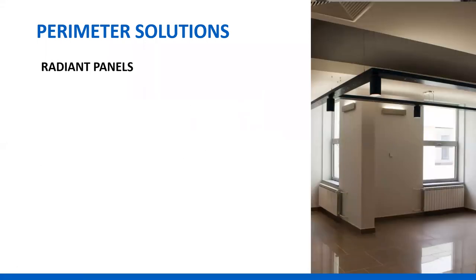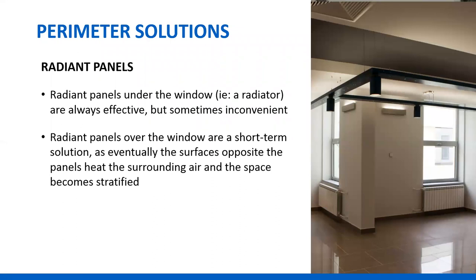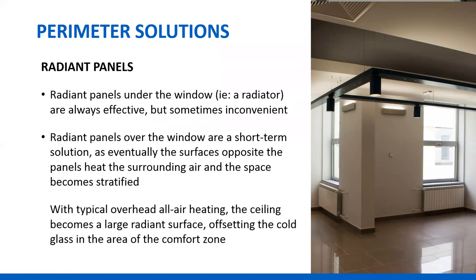Radiant panels have often been located above a window. If you're seated at a desk next to a radiant panel, your feet are in the shadow and it gets cold on the floor. Secondly, radiant panels tend to heat the environment exposed to them — like desks and furniture — which then heats the air and the room becomes stratified. I would recommend radiant panels only in a corridor, not where people are spending a lot of time. What we have found is that with all-air heating from the ceiling, the ceiling tiles warm up and become a large radiant surface, which tends to offset the radiant effect of a cold window — in tests we found neutral radiant more than two feet from the window.